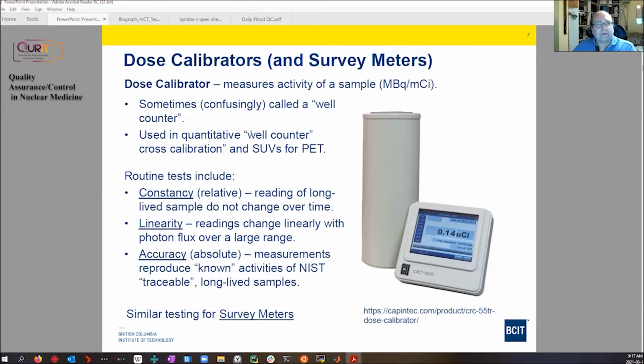So this is very important in PET for quantitative PET, where we do a well counter cross calibration. That is, we use a measurement of the activity in a sample to calibrate a PET scanner for absolute activity concentration measurements and for evaluation of clinical SUVs. Clinical SUVs, we're not talking about sport utility vehicles. I hope that at some point you've run into the term standardized uptake values. This is a semi-quantitative number that we use to assess whether lesions are likely malignant or benign. And I'll talk about that a little bit later.